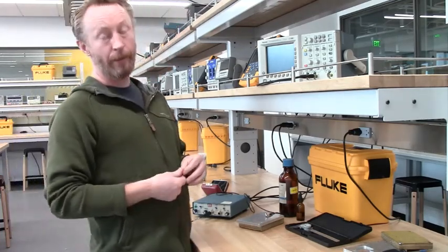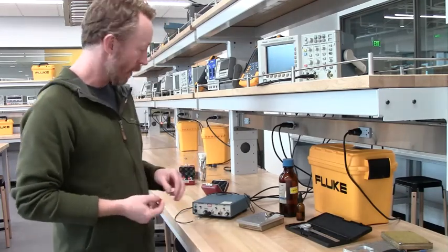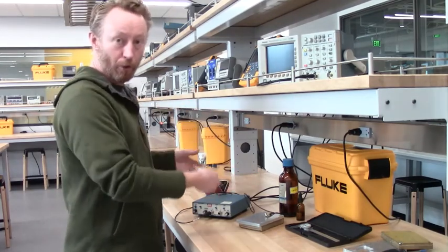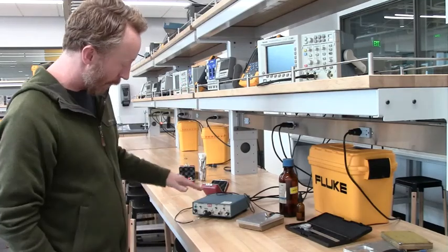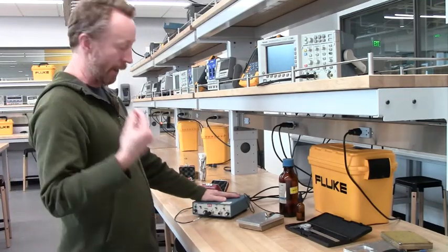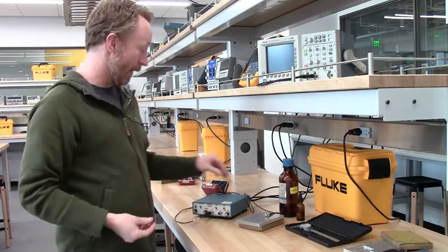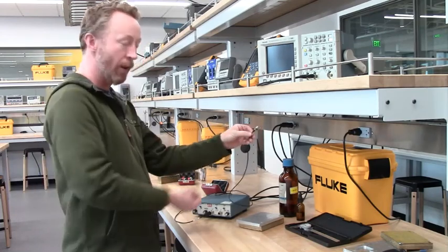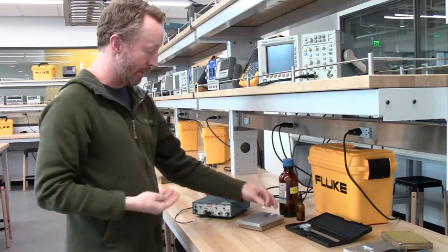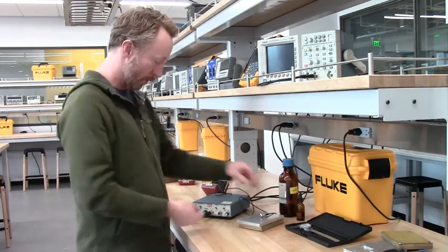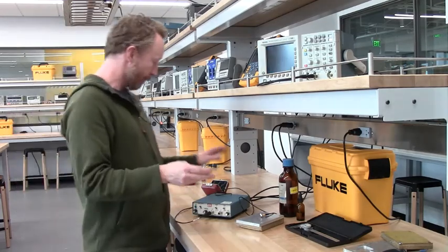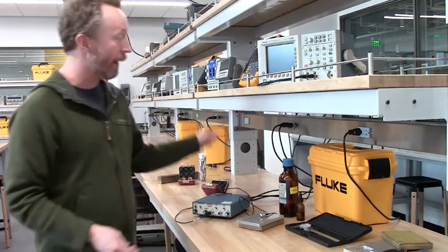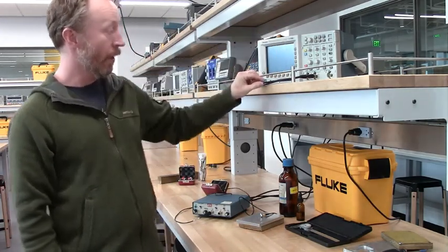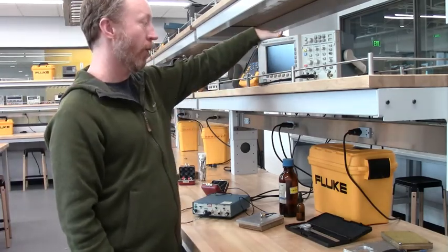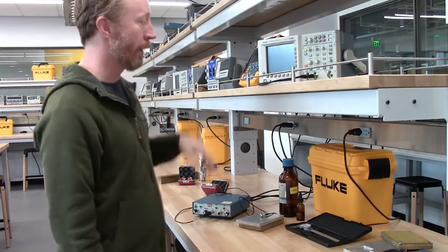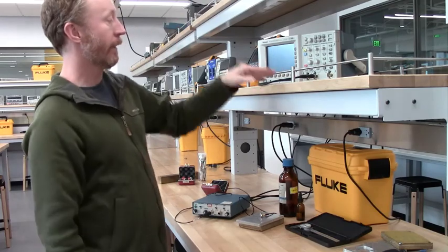The big picture is that we're using ultrasound for non-destructive testing. I'll bring you in closer so you can see this equipment better, but again, we have this pulse echo unit. It transmits and receives ultrasound, so it uses a piezoelectric transducer. It sends it, it receives it. So we're just going from a coax into the unit. I have a sync and the signal coming out the back, and we're running these into an oscilloscope. I have the sync in channel 1 because by default this will trigger on channel 1. We'll get a more stable image that way. And then I have my signal coming into channel 2.